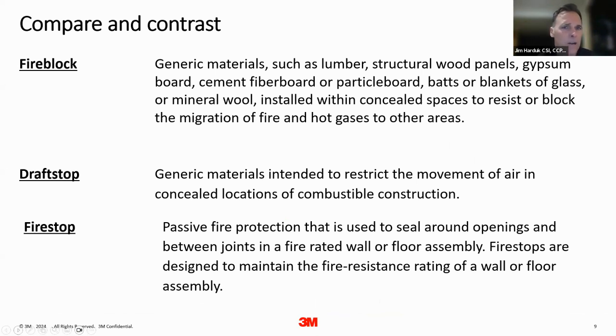We'll talk a little bit now about fire block. Fire block is just any type of generic building material that's used in a concealed space to resist the spread of fire and hot gases. So typically, when we're talking about fire blocking materials, we could be talking about lumber, plywood, gypsum board, fiber cement board, even fiberglass batt insulation and mineral wool can be used for this application. The next term I want to talk about is draft stop. These are generic materials, and they're just intended to restrict the movement of air in concealed locations. Typically, when we're talking about draft stop, we're talking about residential construction. You don't usually see a requirement for that in commercial construction.